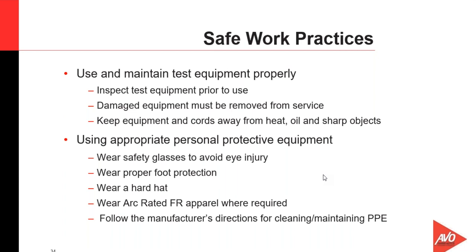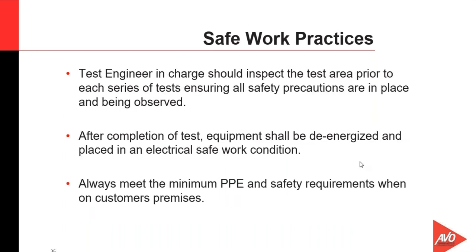Other safe practices: the test engineer in charge or test technician in charge is required to inspect the test area prior to each series of tests. And we'll go through that a little more in depth in the next few slides. Prior to each series of tests, we're trying to make sure that all the safety precautions are in place, all the PPE items are in place, the test area is secure, and there are no unqualified or unauthorized personnel in the test area. After completion of the test, the equipment needs to be de-energized and everything should be placed back in an electrical safe work condition.